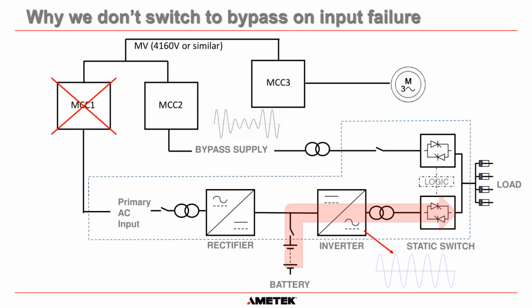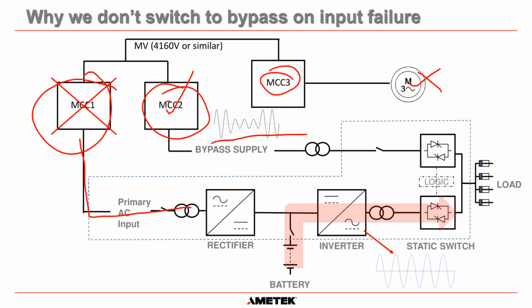And here's a block diagram of what that looks like. Let's say MCC1 has gone completely down, and that's what feeds the AC input into the UPS. If MCC1 has gone down, MCC2 is still healthy, but the plant is going to start putting things into safe modes of operation. You can see here that even MCC3 is connected to the same HV bus. So if we start turning off pumps and do a lot of different things, then the voltage at MCC2 could look like this for a short period of time while the plant stabilizes because of MCC1 failing. And if we transferred to bypass, that voltage would be seen on the load circuits there, okay?